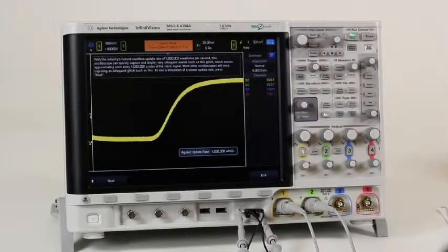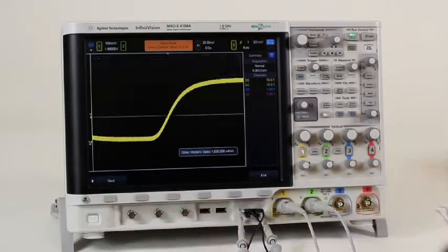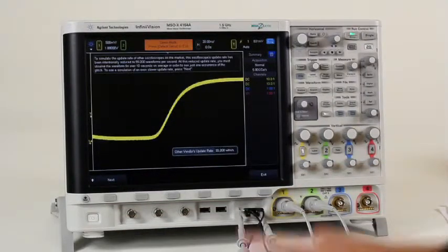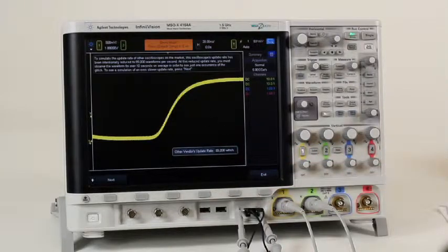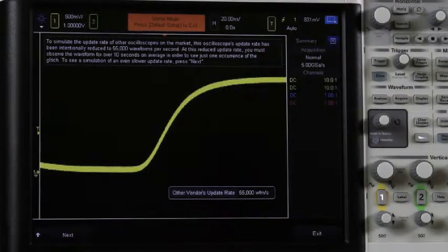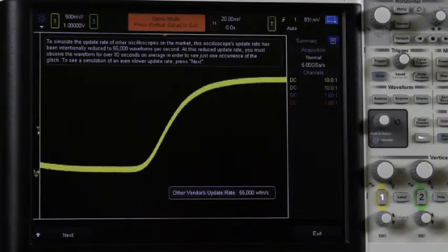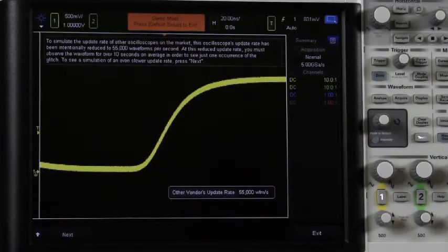We can detune the 4000X series scope update rate and simulate the update rate of another vendor's 55,000 waveforms per second update rate. If you wait long enough, the scope may catch it. But given an engineer's likely debug behavior, they could have easily moved on to the next test point before the glitch was ever captured and displayed.